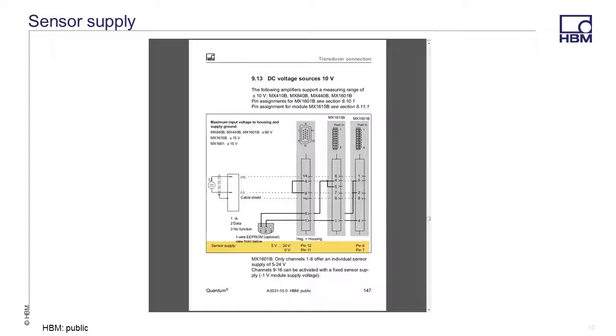This is the wiring diagram for a 10-volt output sensor. Typically, sensors that have a 0 to 10-volt output require sensor supply. Some QuantumX modules can provide 5 to 24-volt sensor supply. Be careful to check your current requirement for your sensor, as the QuantumX modules can only provide 0.7 watts per channel and a total of 2 watts per module.